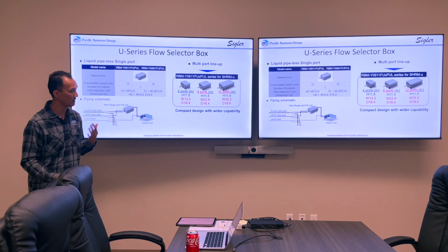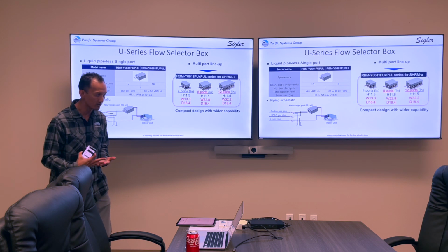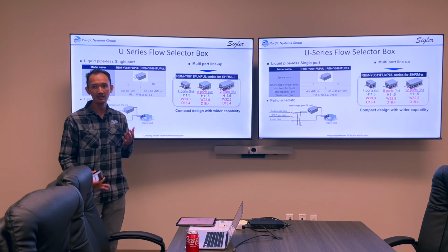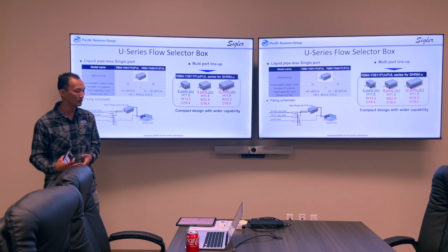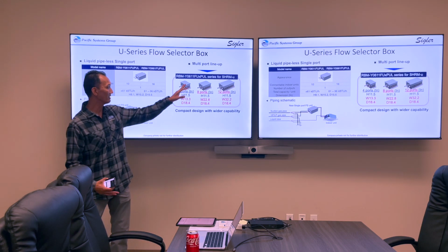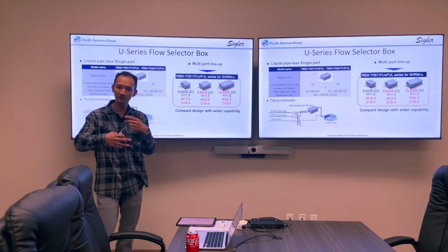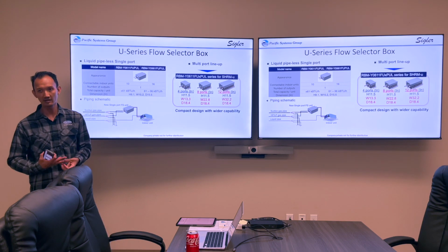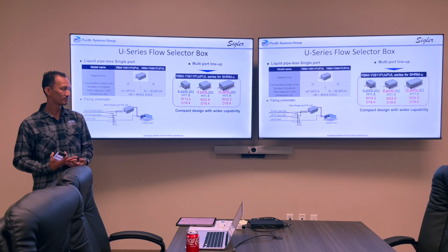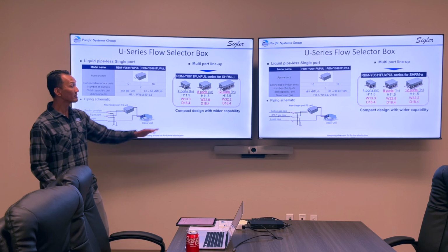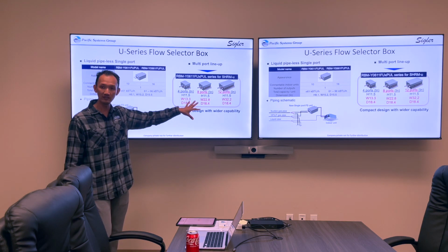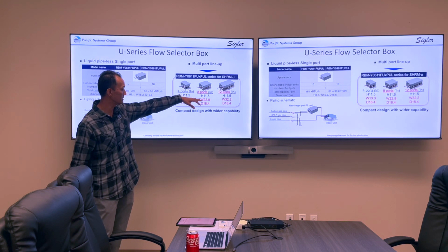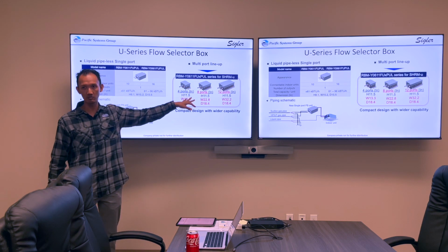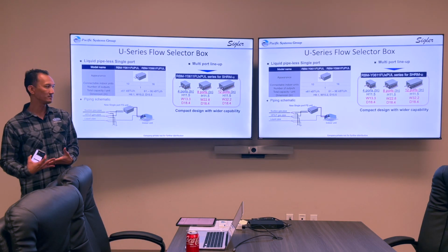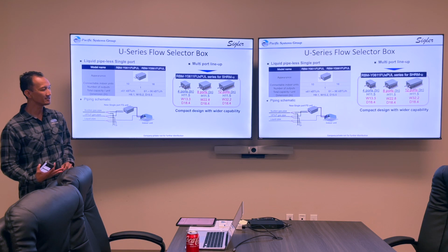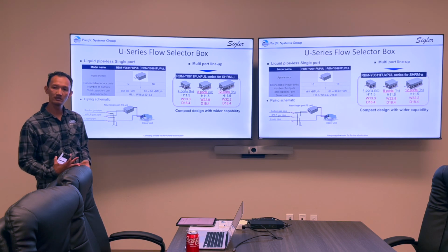And like I said, all of our VRF fan coils have leak detectors built in. All the logic is built in, so if something were to happen, it would tell whichever port to close, the fan would run, and the outdoor unit would shut off. I think it's going to be easier on the three-phase side, because we have this for heat recovery also, with flow selector boxes that have the valves built in. So it's going to be even less of an issue on the three-phase.